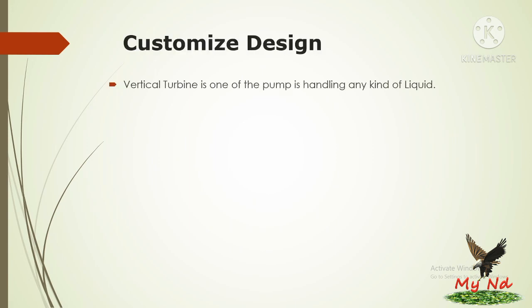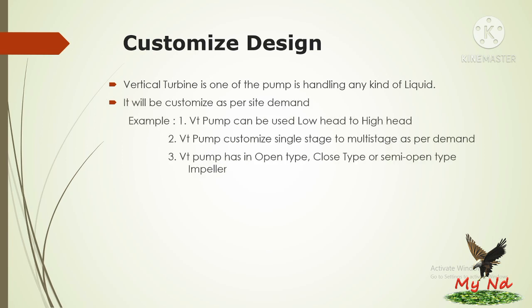Customized design. The vertical turbine is a pump that can handle any kind of liquid. It will be customized as per the site demand. A VT pump can be used from low head to high head range. A VT pump is customized from single stage to multi-stage depending on the site condition. A VT pump has open type, closed type and semi-open type impellers. A VT pump handles any kind of water.